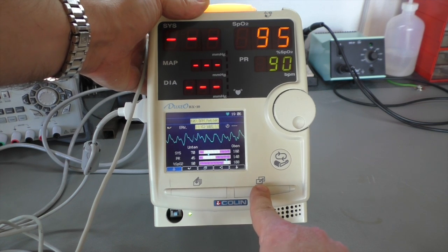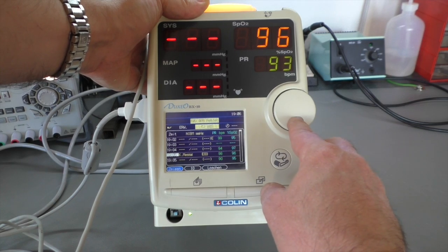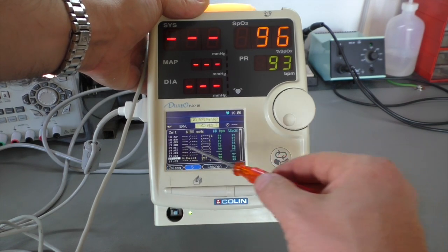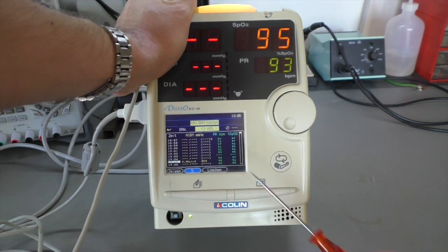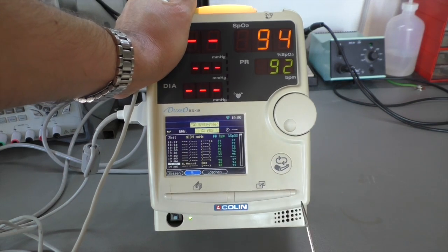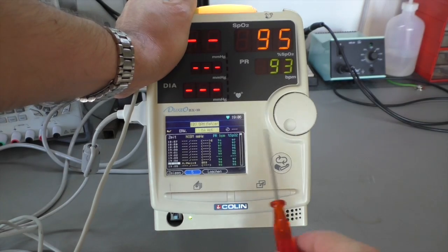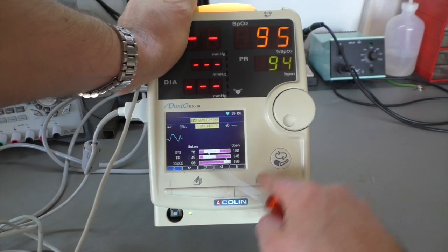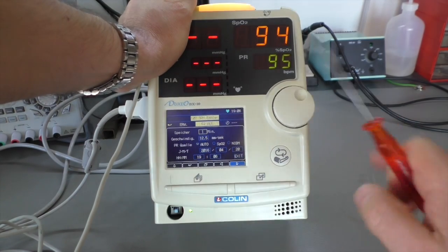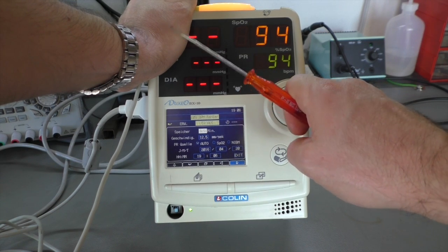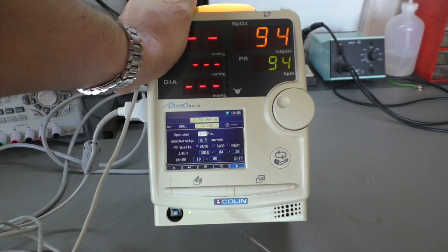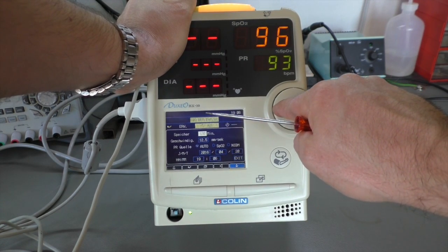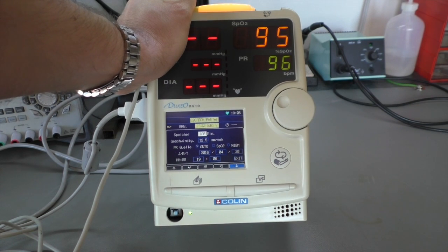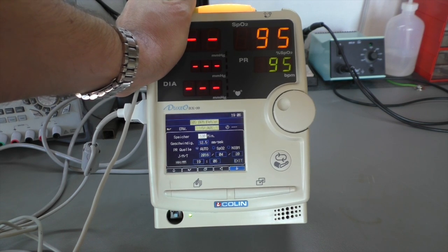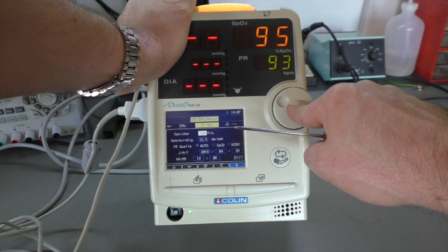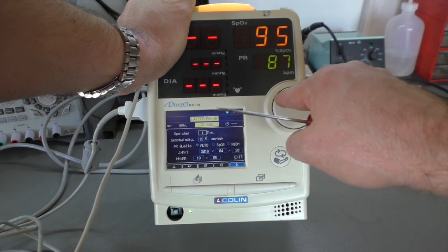Okay, what can we do else? There is a menu select button. We have different screens. For example, here is a list of the measurements. They are from yesterday. No, maybe from today. So I have every minute here. I set it like that. You can choose. Let me see. On that screen, here you can say every minute, or every 2 minutes, half a minute. So that's the shortest interval to log the data, so 30 seconds. And the longest interval is 2 hours. So if you have to monitor a patient for a very long time, you can set it to 1 hour, so it takes one measurement every hour, or every minute, as I like it here.